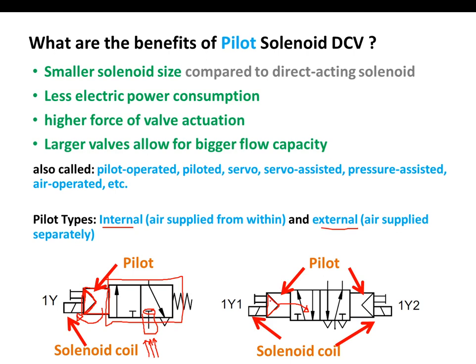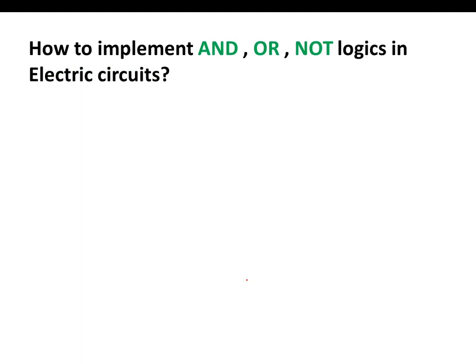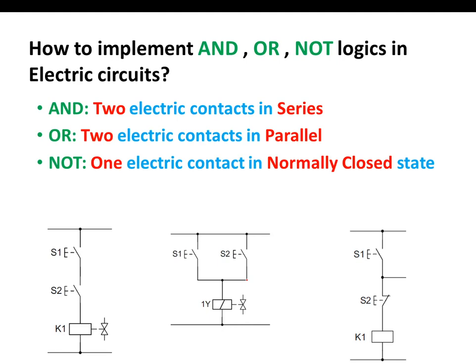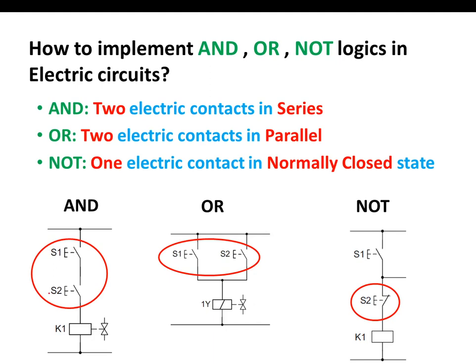How to implement AND, OR, and NOT logics in electro-pneumatics: we are still using these logics, however the way to implement them is different. For AND logic, we combine two switches in series. For OR logic, two switches in parallel. And for NOT logic, it is represented by a normally closed switch.